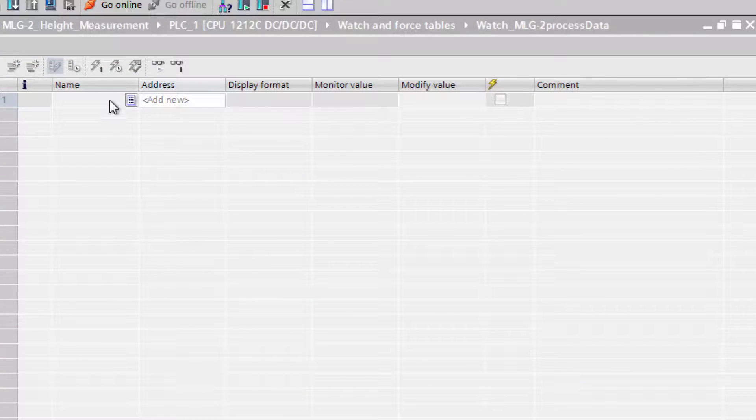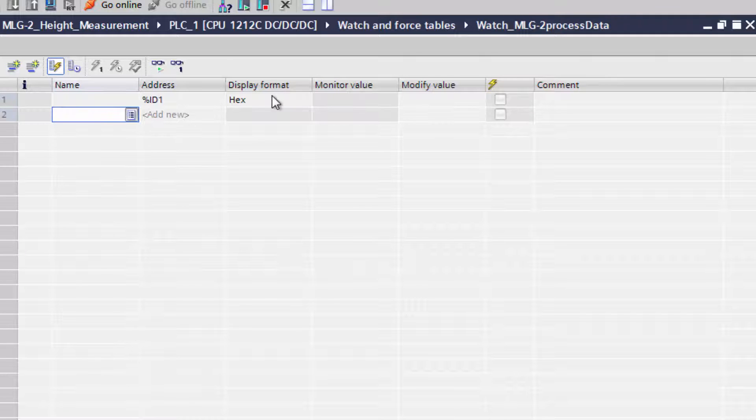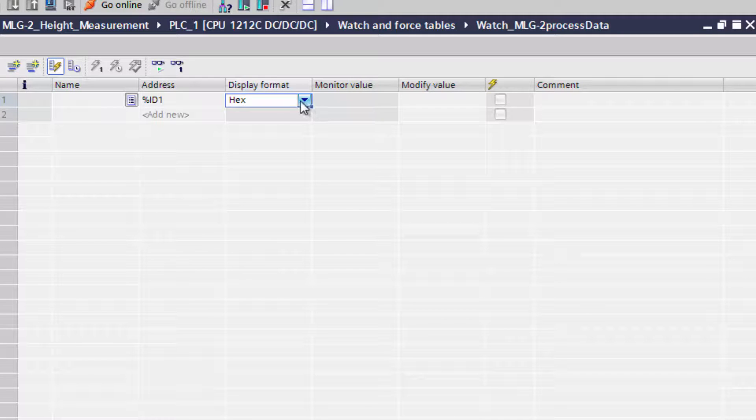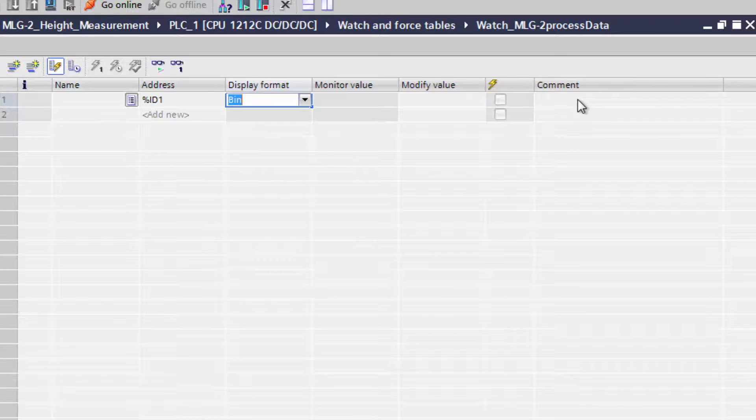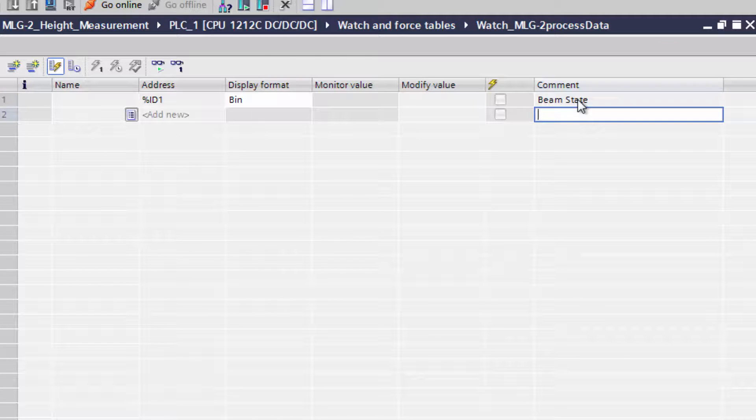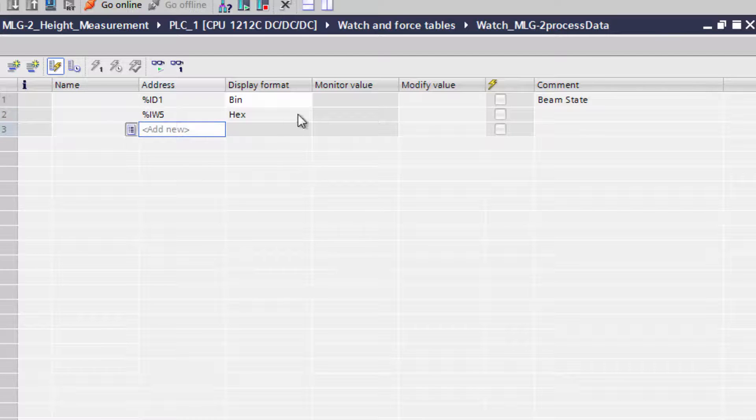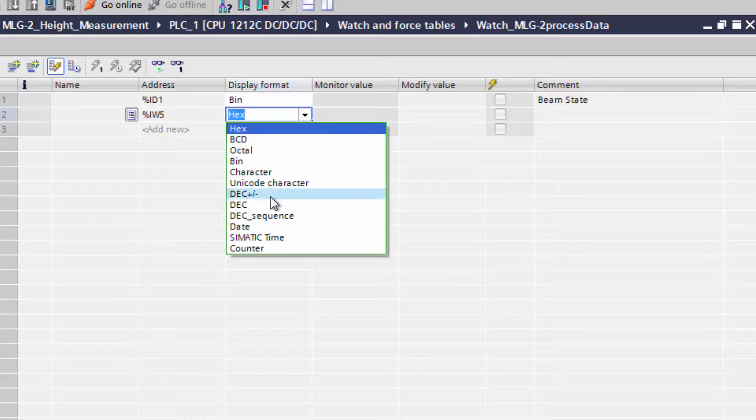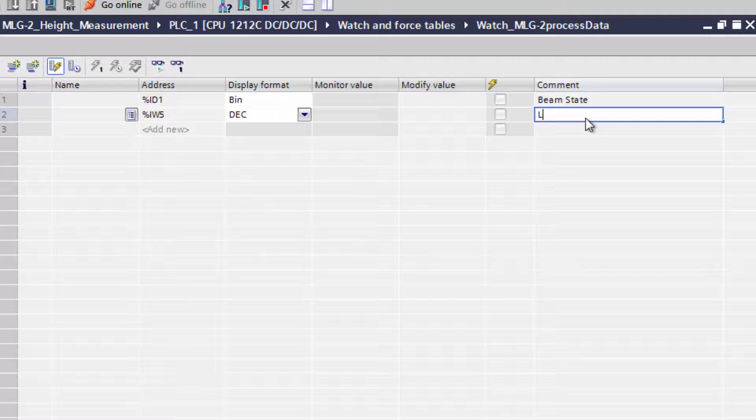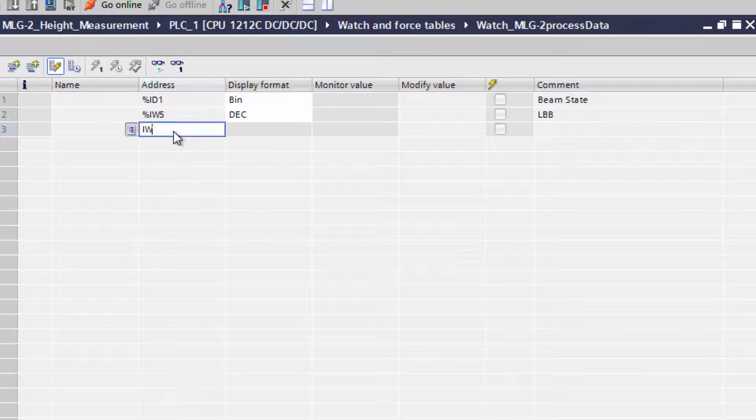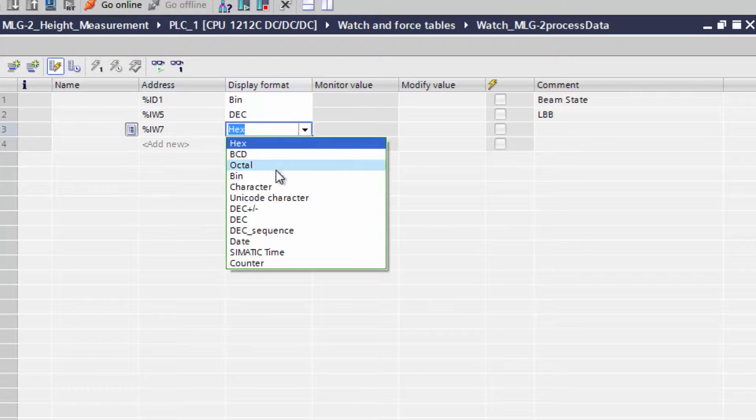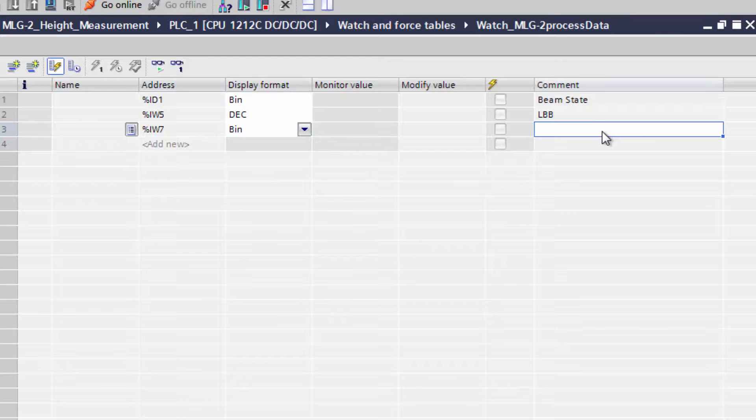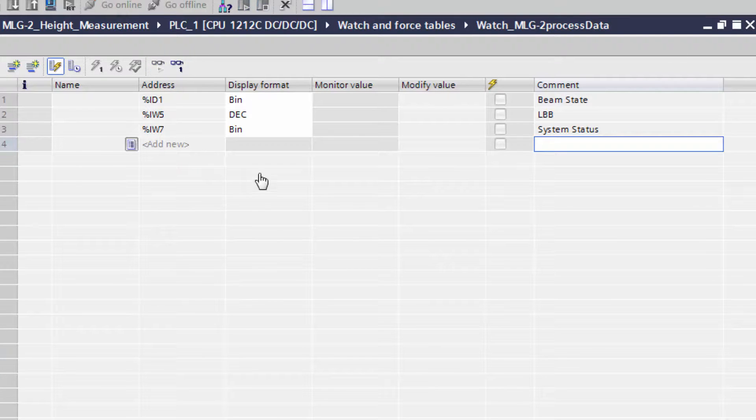For the beam status, the input DoubleWord ID1 is assigned and the format is set to Binary. The input word IW5 is for the last beam blocked and the display format is decimal. Input word IW7 is set for the system status with Binary as display format. 1, 5 and 7 are selected as these are the start bytes of the functions. By clicking on the glasses symbol, the watch table is set online.